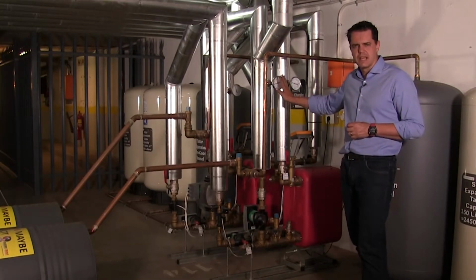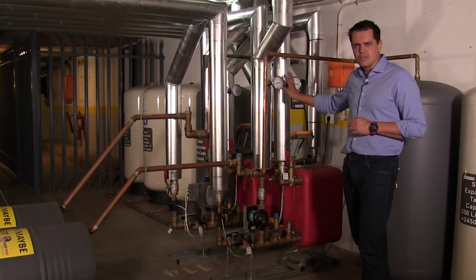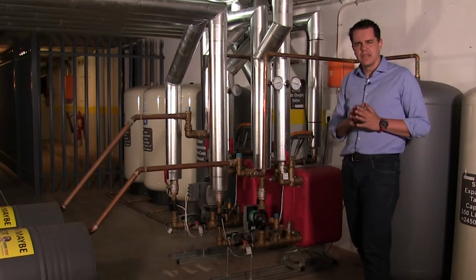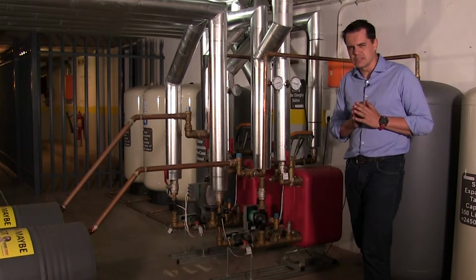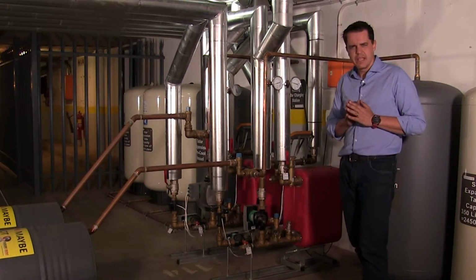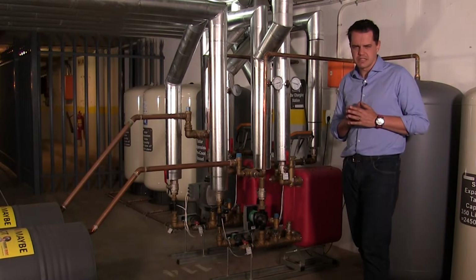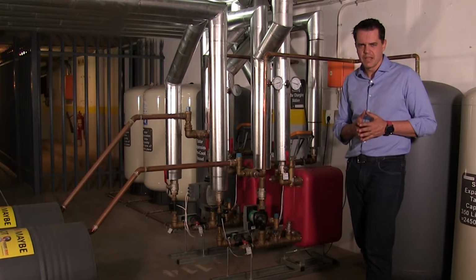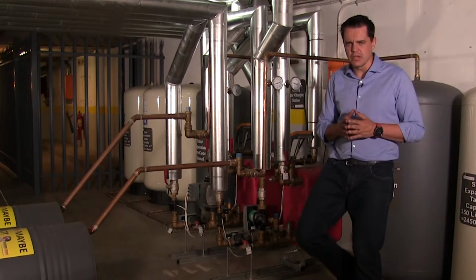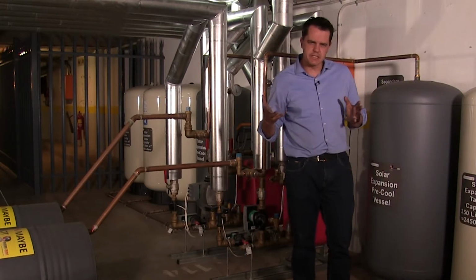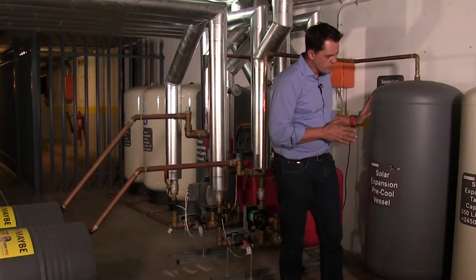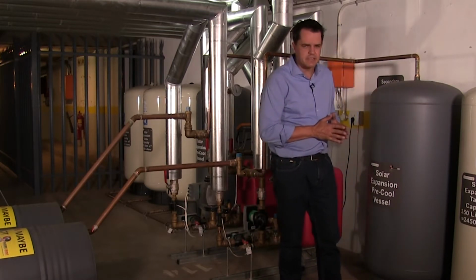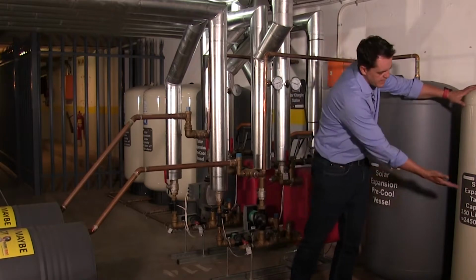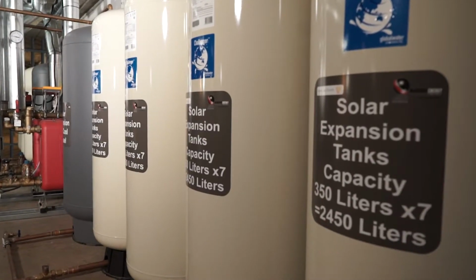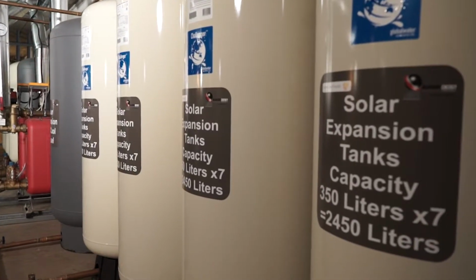If that shows that there's in fact no temperature differential, there's only a few things that could be wrong. Number one is that at some point the system has gone into overpressure, and again, similar to our other plants, if the system goes into stagnation, we've got our solar expansion tanks, the membrane expansion vessels. Again, these vessels have got a rubber membrane in there, half liquid, half air.